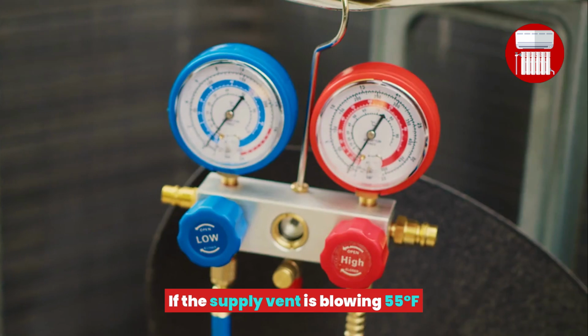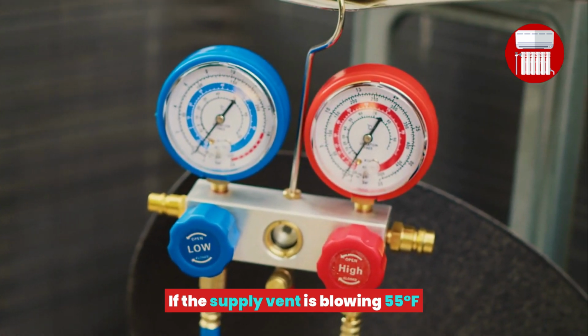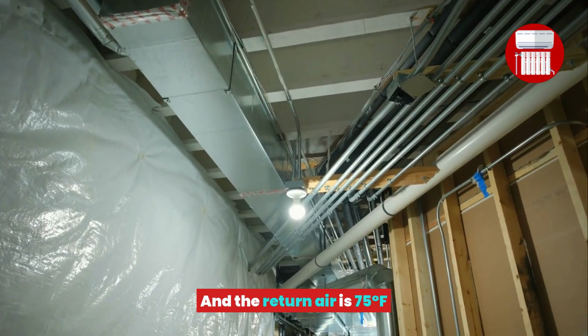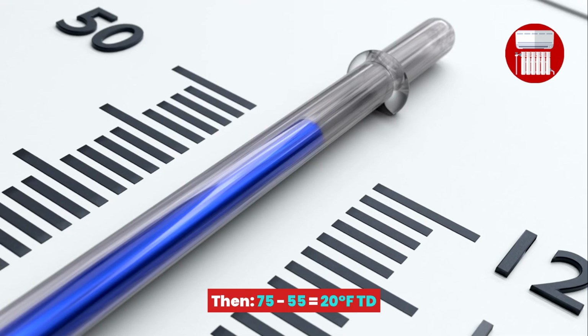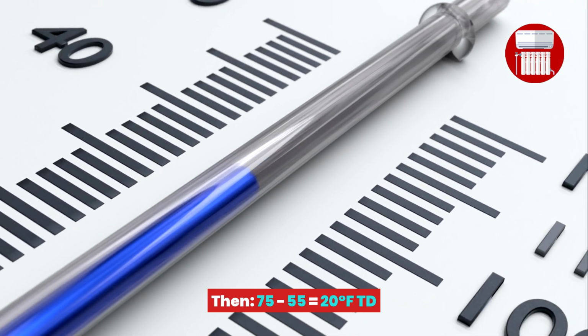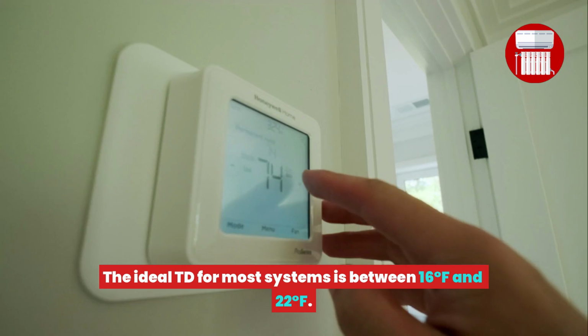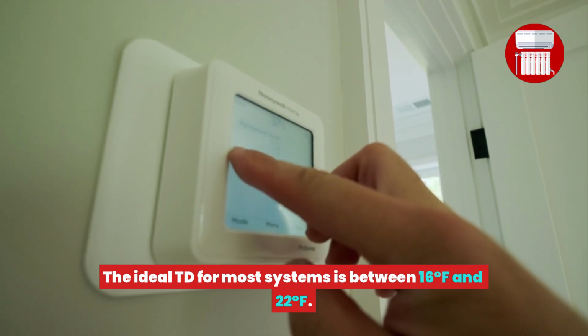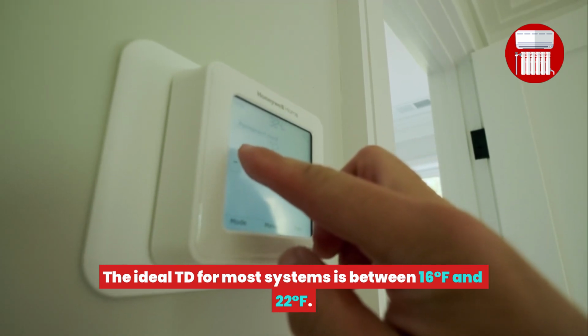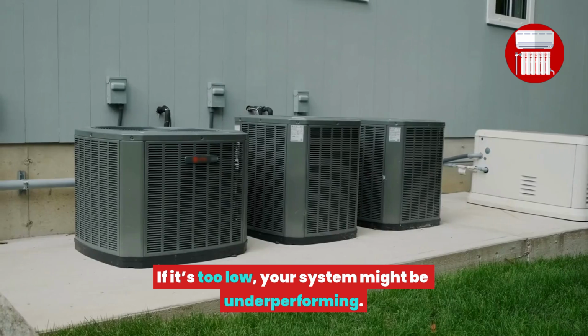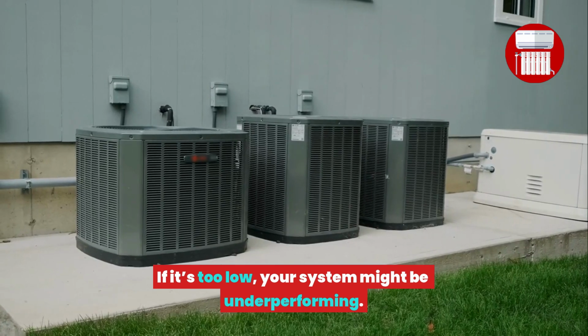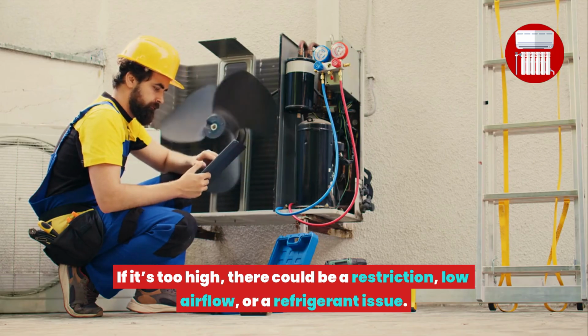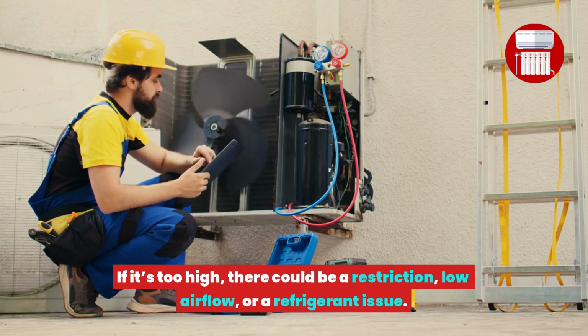For example, if the supply vent is blowing 55 degrees, and the return air is 75 degrees, then 75 - 55 = 20 degrees Fahrenheit. TD ideal range. The ideal TD for most systems is between 16 degrees Fahrenheit and 22 degrees Fahrenheit. If it's too low, your system might be underperforming. If it's too high, there could be a restriction, low airflow, or a refrigerant issue.